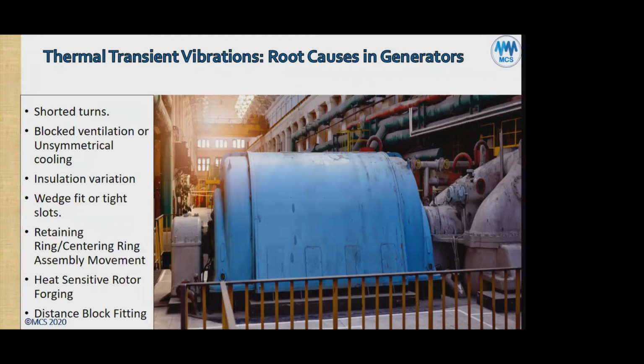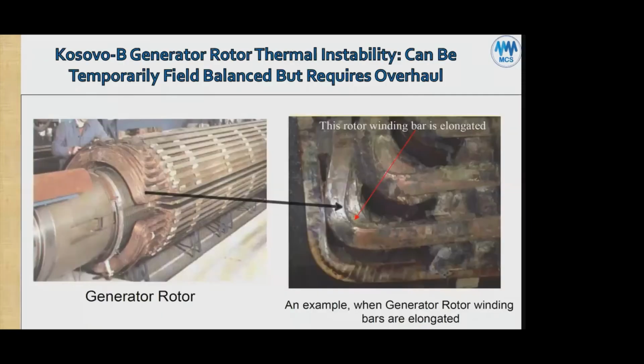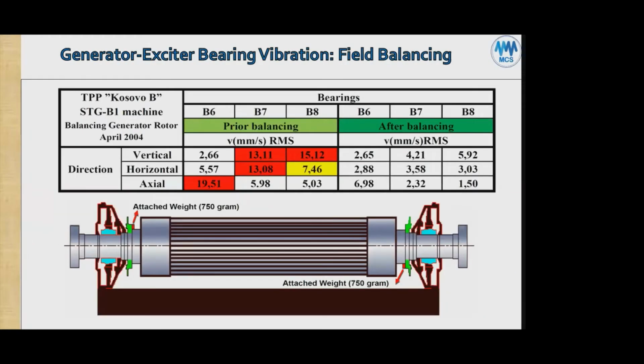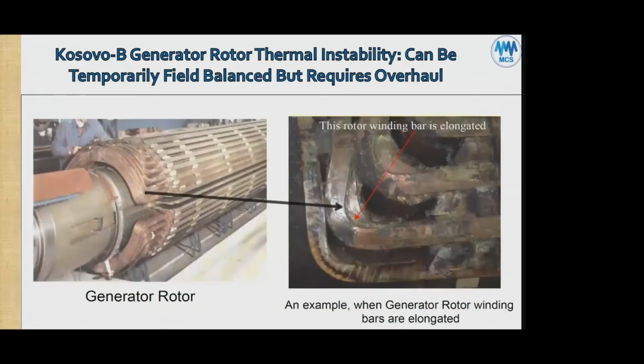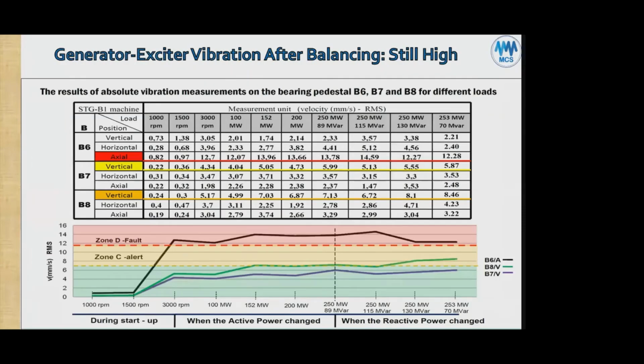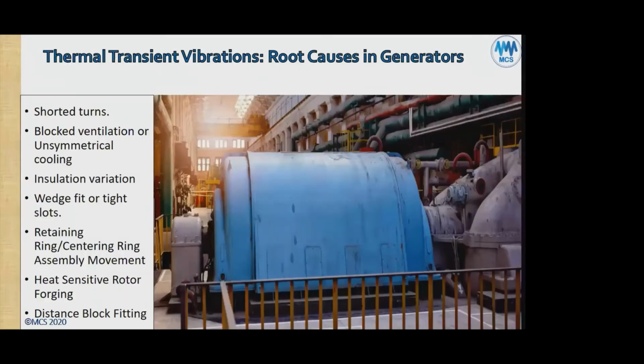So generator rotors are what we see up here. Generator rotors have many mechanical components and electrical components, and there are many sources where they can have thermal transients due to internal problems. You have to be careful of thermal transients in generators, because the generator can be moving toward a more dangerous condition, such as a short circuit in the rotor itself. So it has to be carefully analyzed when it's going through heavy thermal transient vibration.